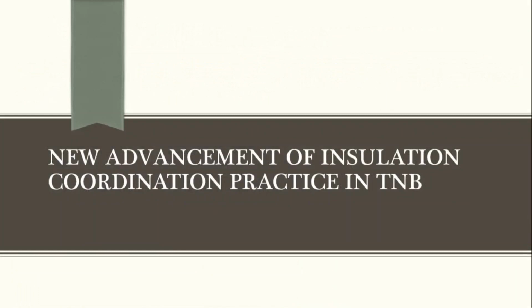Okay. Now, I'd like to talk about the new advancement of insulation coordination practice in TNB. Okay, we go back to our strategy. We deviate, we insulate, we dissipate, and we need to coordinate all the DIDs, right? Okay, here's an idea. Can we dissipate the lightning current to the air? By doing so, we don't need a good earthing value or earthing measurement, right? By dissipating the lightning current to air, and air can quench the arc of the lightning current, we don't really need the minimum requirement of this earthing, right? So is that possible?